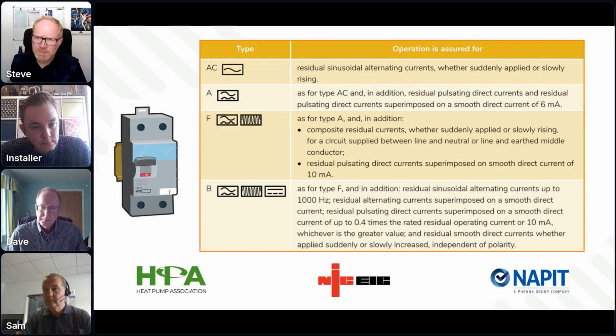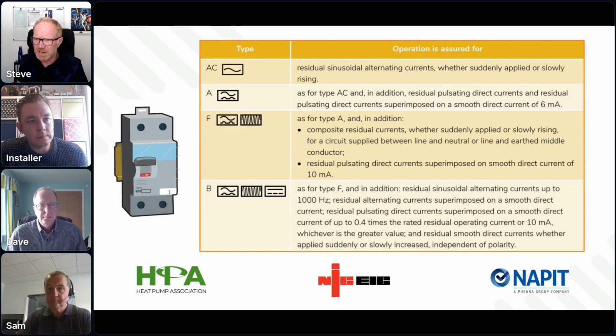Yeah, on first glance, if you get to step 3, it seems a bit scary, but the guidance in the HPA document is very clear, especially in table 1. If the manufacturer's instructions do not specify a particular type of RCD, which Sam's just covered, then we've got to determine the electrical characteristics again. So what is the DC coming back, at what levels, and is it pulsating? Is it smooth? Which again can seem a bit tricky.